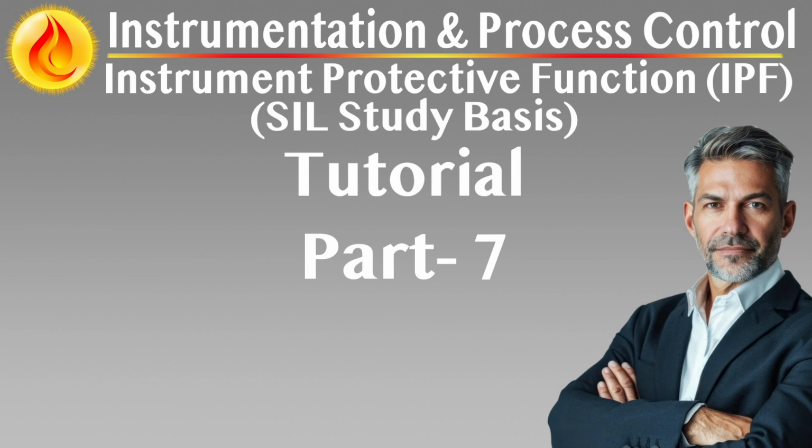Verify SIL compliance. Confirm that the actual probability of failure on demand, PFDavg, remains within the allowable limits defined by the SIL target, based on failure data, test coverage, and interval. Identify hidden failures. Detect latent faults in sensors, logic solvers, or final elements that may not be apparent during normal operation but could prevent correct response during a real event.